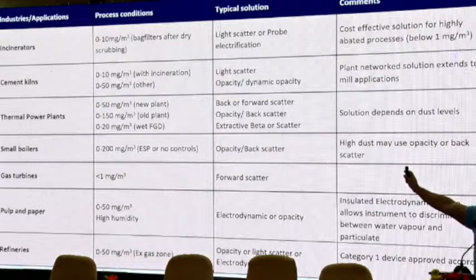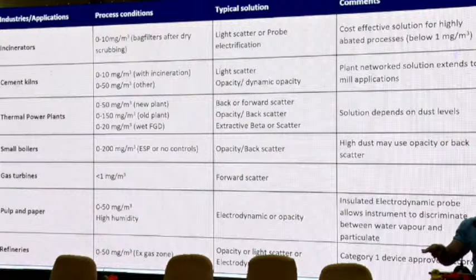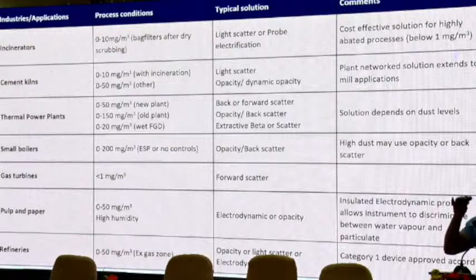Based on this, let's think about the thermal power plant, where we can find the ideal condition for equipment selection. If the range is 0 to 20, which is pretty low, forward scatter is most suitable. For 0 to 50, backward scatter or forward scatter will also work. For 0 to 150, opacity and backward scatter can also work. So this is how you understand. This bit of knowledge is also important when you buy equipment from a vendor.